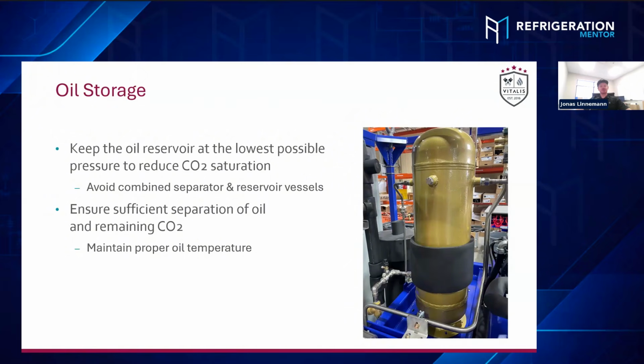But typically it's not really affecting the oil differential pressure, because if your receiver pressure is at the same pressure as the crankcase or suction pressure, the whole system will not work anymore. The compressor will survive without getting oil refilled for 1 or 2 minutes, but the system itself will fail if you really run into that major problem. Have you ever seen reservoirs fill with liquid CO₂? Yes, I've seen that. I once built a test system in R&D, so it wasn't a client project. So that's totally fair to see those things.